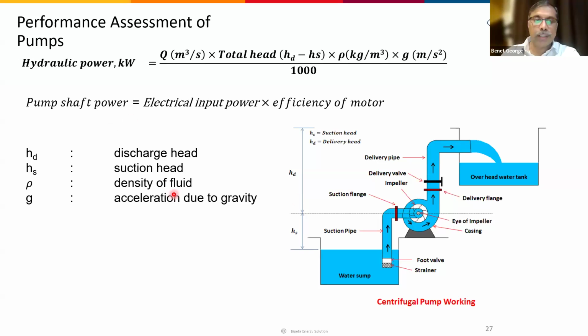In this case, Q is the flow in cubic meters per second. Total head is discharge head minus suction head. Here it is sucking, so it will be HD minus HS, otherwise it will be HD plus HS. Then rho is the density of water, and g is the acceleration due to gravity, 9.81. So here we get the hydraulic power, and the pump shaft power we can measure using a clamp-on power meter.